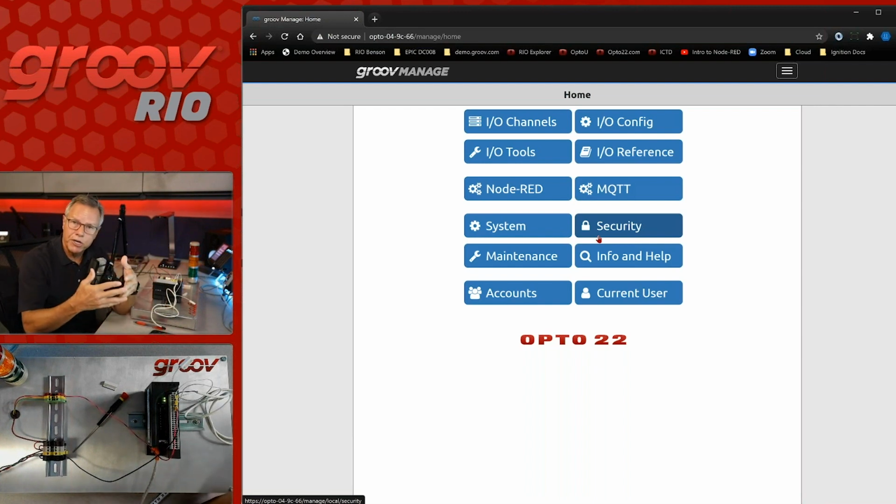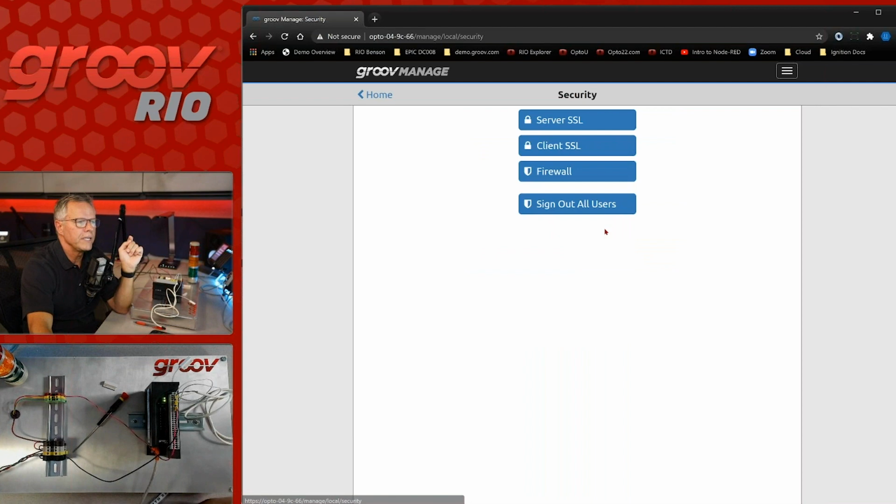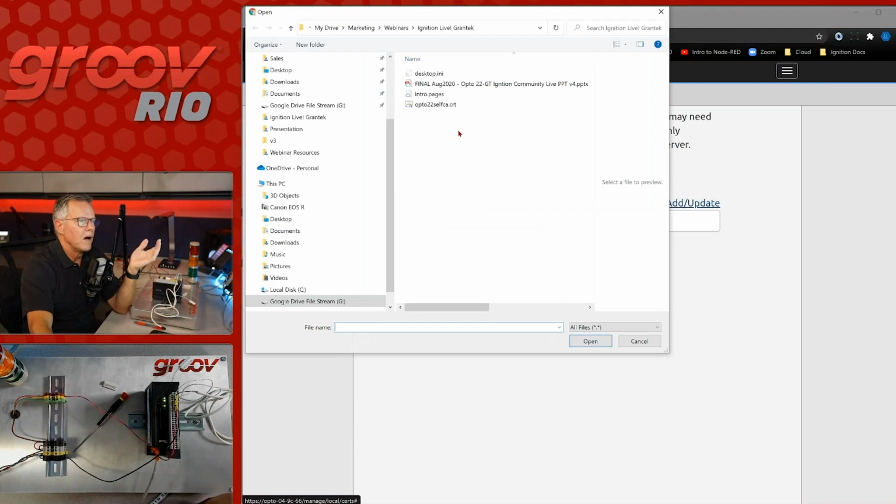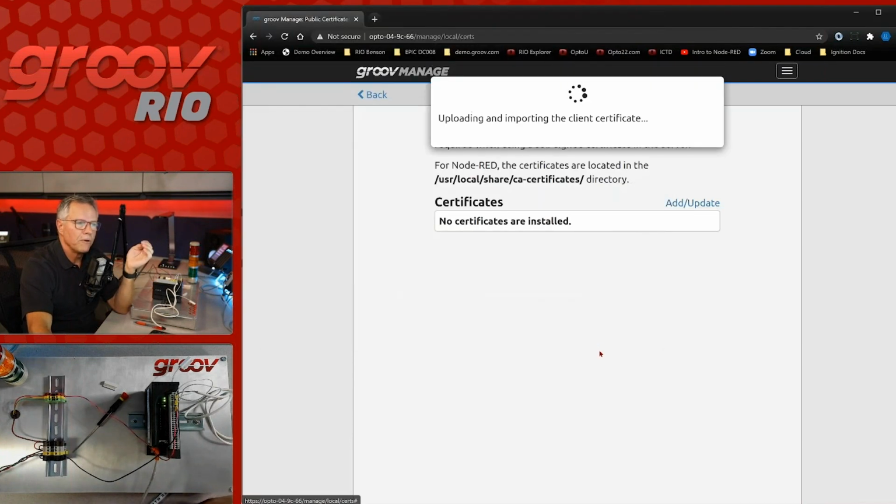Now, my broker is a Chariot broker from my friends at Cirrus Link Solutions. They provided us a Chariot broker. We're running it on AWS, just a small EC2 instance, a T2 micro, just a small little guy. And it's a very efficient broker. And in there, we've created a security certificate. So I need to put it here in the Rio. So the beauty is that all those tools are built into the Rio to go and get my certificate. I'm going to get it off my hard drive, and I'm going to upload it to the device. So what happens here is that when I make that initial connection to the broker, I'm going to exchange those security certificate keys to ensure that, one, I'm talking to the right broker, and two, I'm going to create an encrypted tunnel that I'm going to move all of the data through.